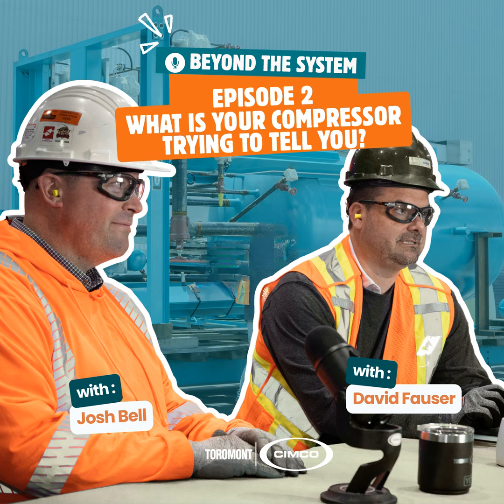Okay, and really there's different types. Like there's your reciprocating, your screw. What other sort of compressors would we look at in a refrigeration system? Yeah, I mean, on some of the smaller, maybe mechanical dehumidifiers, you might get what they call a scroll compressor. On some of the large air conditioning applications, you would see a centrifugal compressor. In our industry, HVAC, refrigeration, you're going to see a lot of small HVAC compressors, either the scroll or the reciprocating machine, but they would be a hermetic machine, meaning they're mechanically sealed and they typically can't be serviced. That's why if your dehumidifier compressor fails, you typically see mechanics coming in and replacing the compressor with a new one. There's really no saving those.